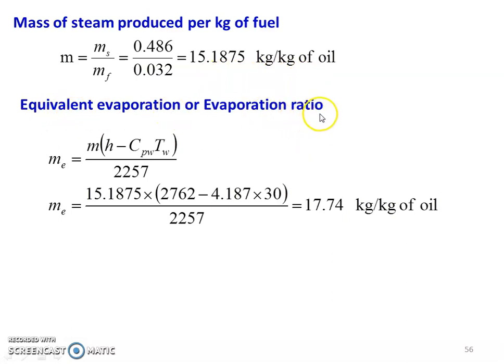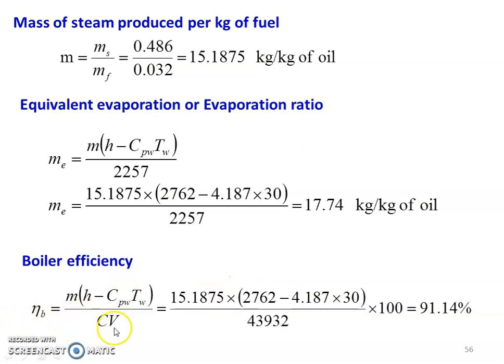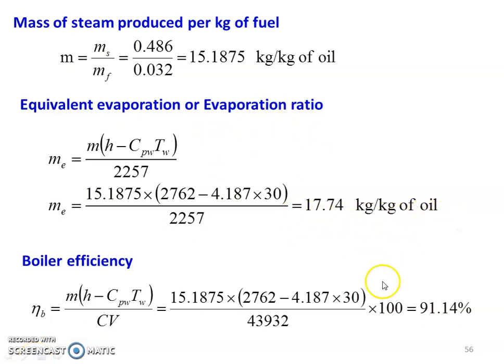Equivalent evaporation, ME equals M into (H minus Cpw into Tw) divided by 2257. So, 15.1875 multiplied by (2762 minus 4.187 into 30) divided by 2257 equals 17.74 kilograms per kilogram of oil. Then we calculate the boiler efficiency: eta B equals heat utilized to produce steam divided by the calorific value, which is M into (H minus Cpw into Tw) divided by the calorific value. So, 15.1875 into (2762 minus 4.187 into 30) divided by 43,932 into 100 equals 91.14%. The evaporation ratio is 17.74 kg per kg of oil and the boiler efficiency is 91.14%. These are the answers to the question.